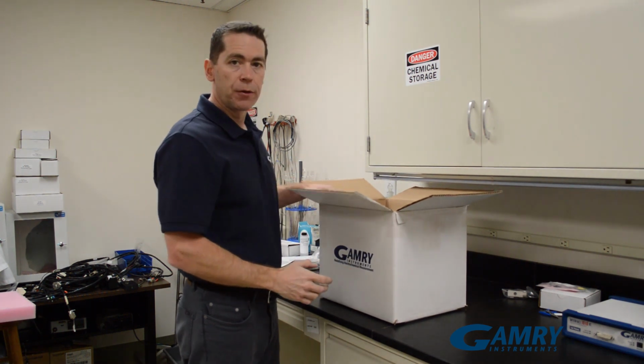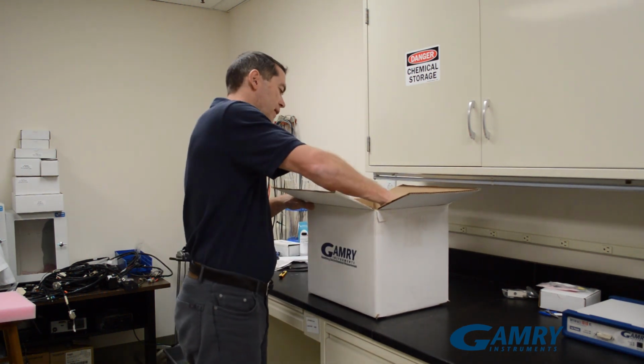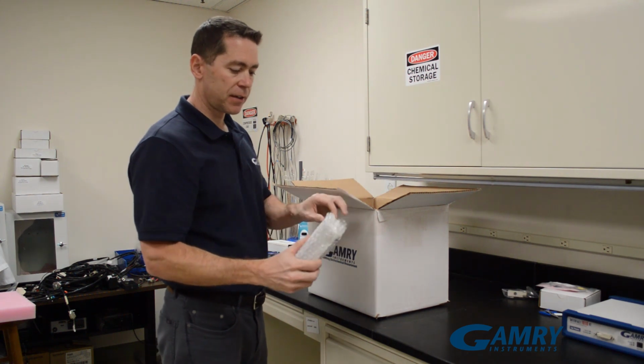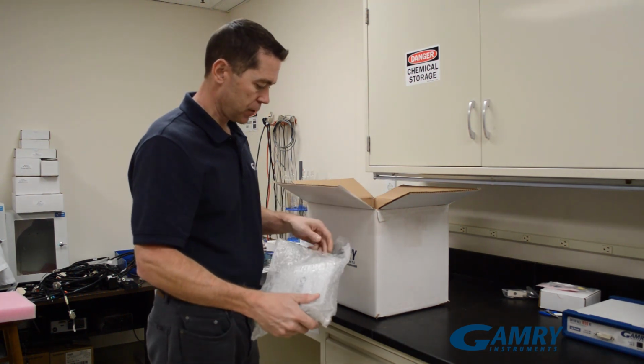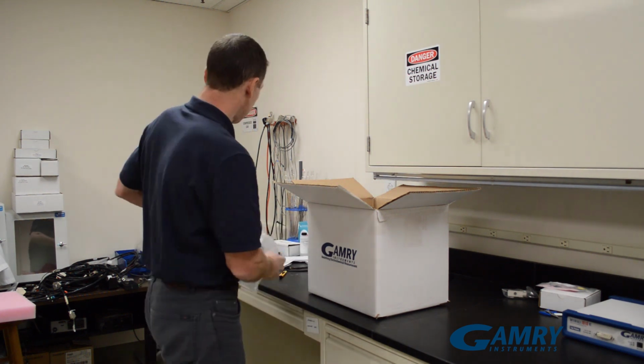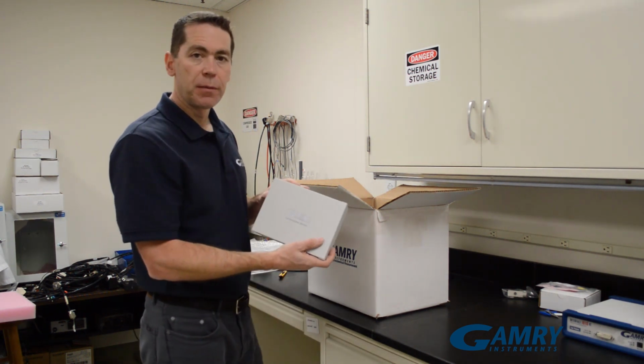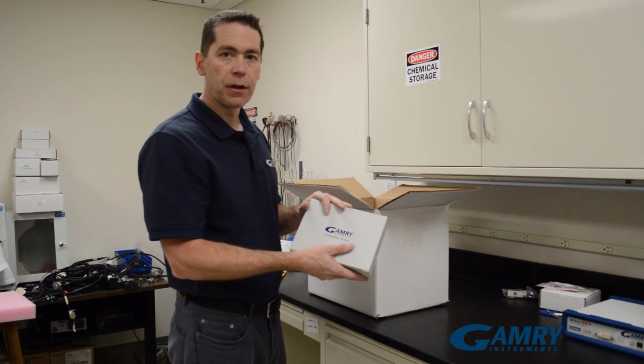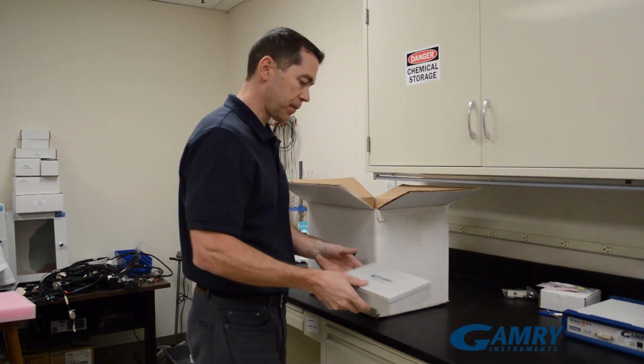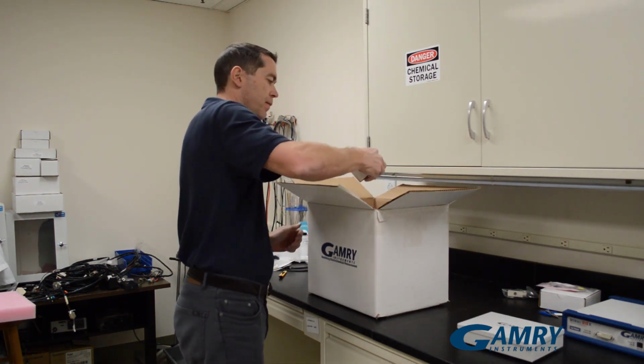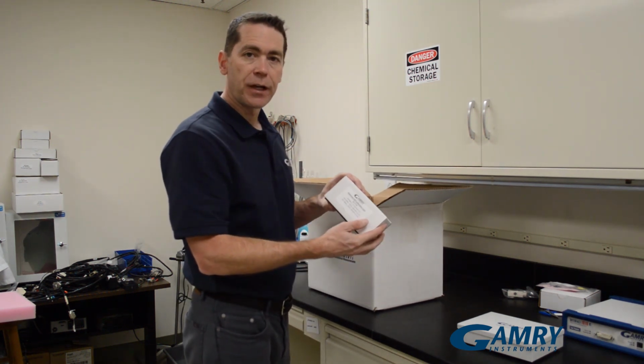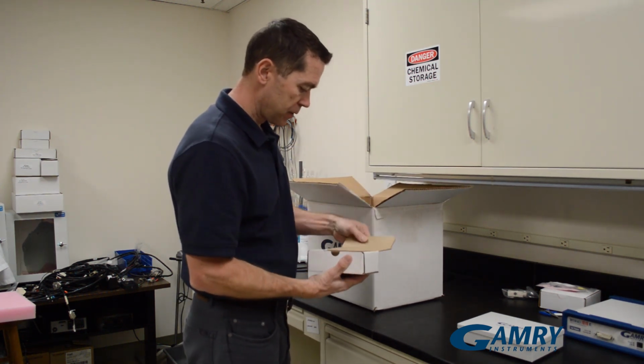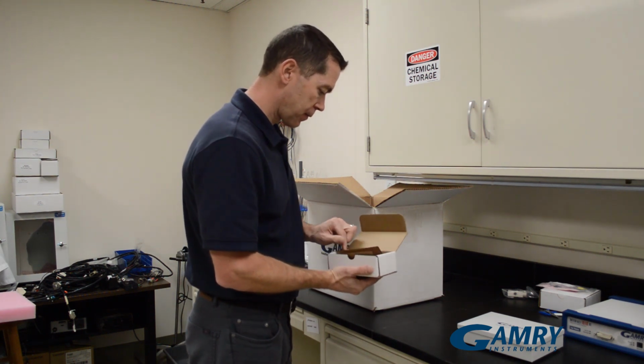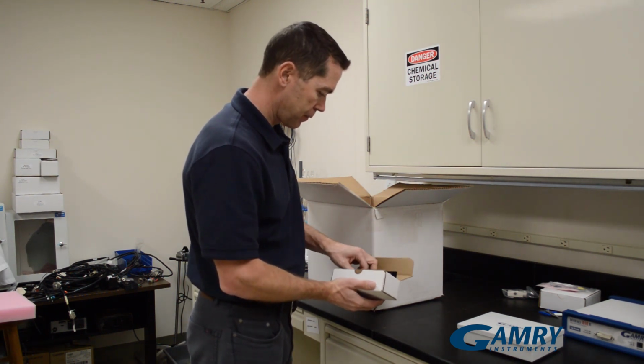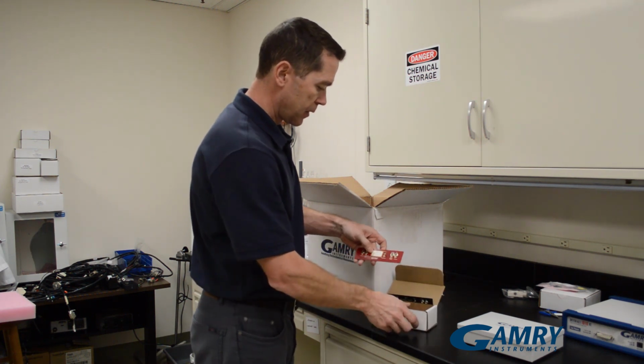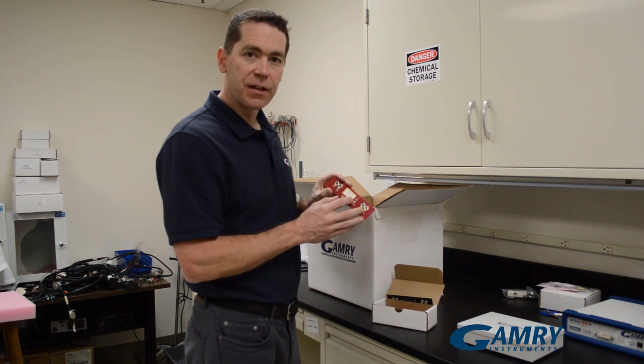So when you first open up your Reference 620 Potentiostat, on the top you're going to have things like the calibration shield. This is a miniature Faraday cage that we would use to run our calibration of the instrument itself. We have two calibration cells. The 200 ohm calibration cell is the standard calibration cell.